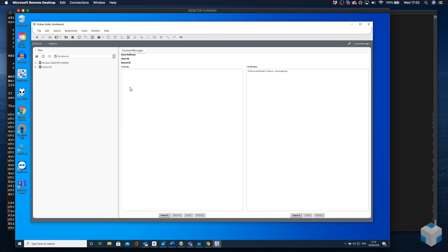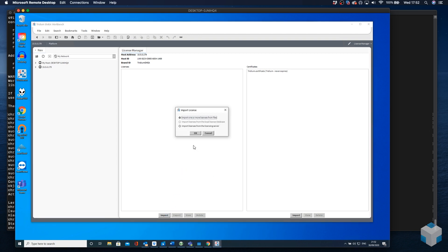Now that we've connected to the platform, we'll go to the license manager. Here we will grab the host ID, this LNX number here, and send it to our Tridium partner for a license. Once we've received that license, we can either import the license automatically from the licensing servers or we can bring those files in manually.